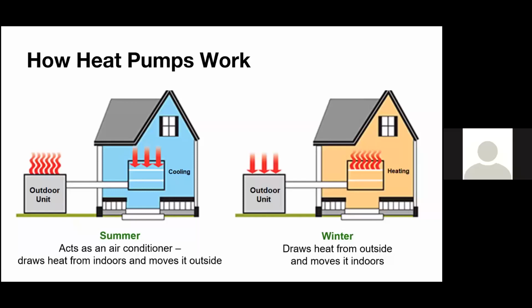But of course, the systems are designed for this. So this is where the term defrost cycle comes in, where the outdoor unit is looking at its condenser coil, and it realizes, because of the amount of heat exchange it's getting, that it might have ice on it. So therefore, that reversing valve will kick in. It'll reverse the cycle back the other way and put that hot refrigerant through the outdoor coil as quickly as it can to melt and defrost that ice, and then it'll go back to heating the inside. Which means when it gets colder, we have to take that into account.